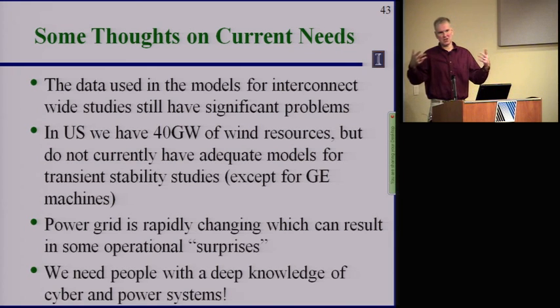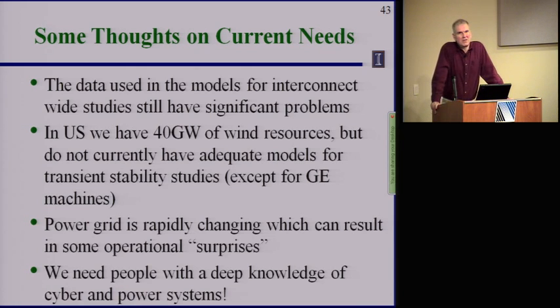You have to have a shock, and the power grid is pretty good at absorbing shocks. After this event, some people got in the news talking about how fragile our power grid is. Our power grid is not fragile - it gets hit by lightning all the time, lines go out, and it keeps on ticking. If you lose 100 megawatts of load, we've got loads in the system where you'll get 200 megawatts from an arc furnace coming on like that. So the power grid can handle some pretty significant disturbances.